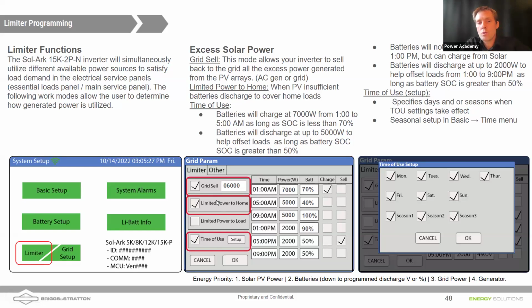This is often useful if you have peak demand charges, right? If you go over a certain threshold, you can use this to limit that threshold. We also have limited power to the load, which, for a Sol-Ark 15K, often is essentially the same thing. But with an 8K and a 12K, remember, you only have a backed up loads panel, and so it's a little bit different wiring. So there are different features for an 8K and a 12K.